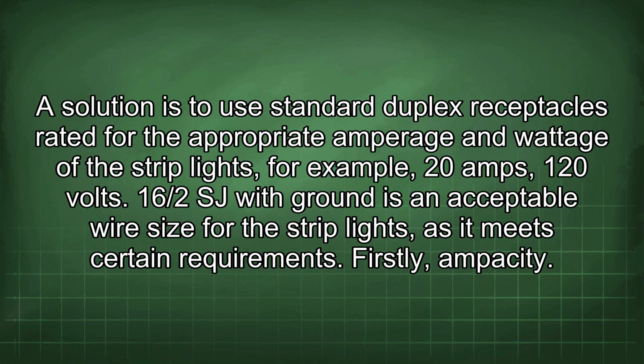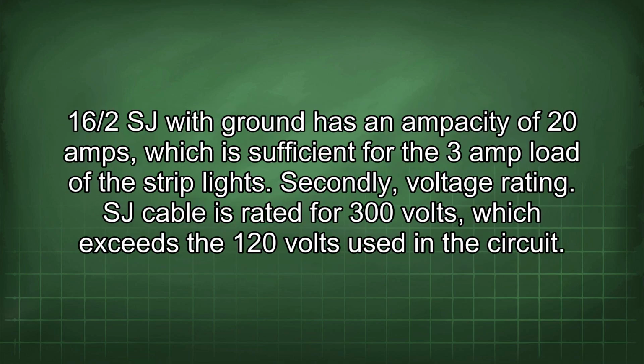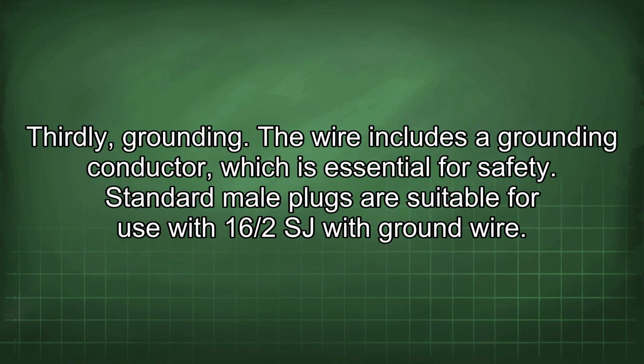16/2SJ with ground is an acceptable wire size for the strip lights, as it meets certain requirements. Firstly, ampacity. 16/2SJ with ground has an ampacity of 20 amps, which is sufficient for the 3 amp load of the strip lights. Secondly, voltage rating. SJ cable is rated for 300 volts, which exceeds the 120 volts used in the circuit. Thirdly, grounding. The wire includes a grounding conductor, which is essential for safety.